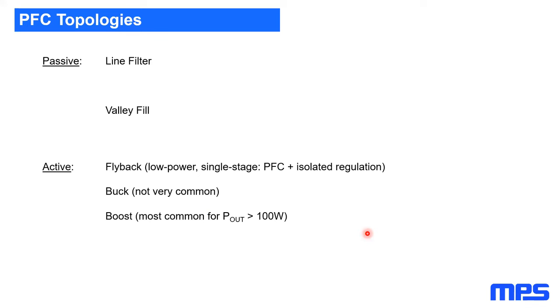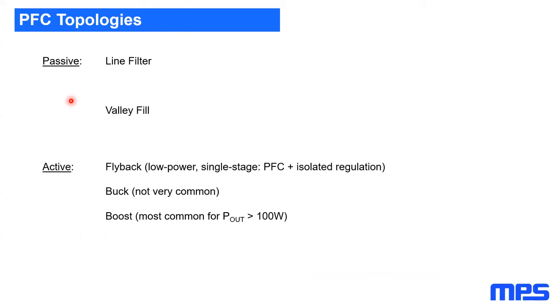There are several ways of doing this — passive or active. The simplest passive way is to use an input low-pass filter that forces the current to be sinusoidal at the frequency of the grid, 50 Hz or 60 Hz depending on where you are. It's very simple, but because of this low grid frequency, it means a large filter with large inductors — not always practical and also costly.